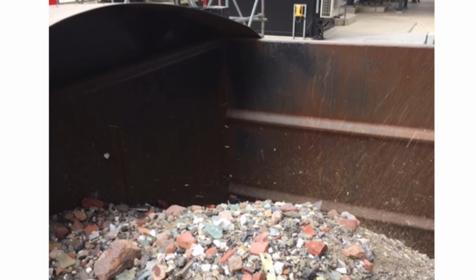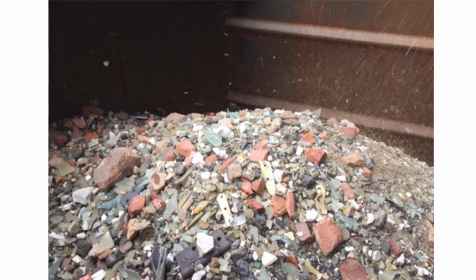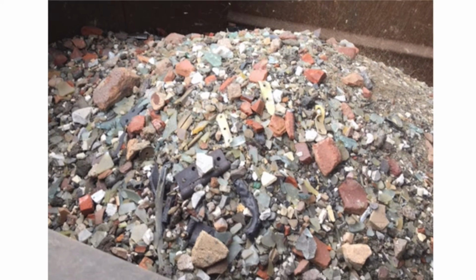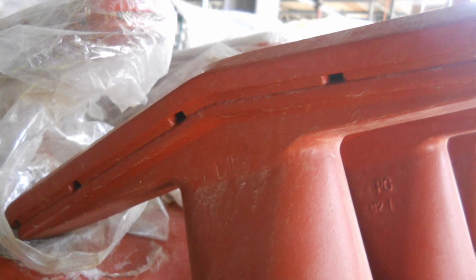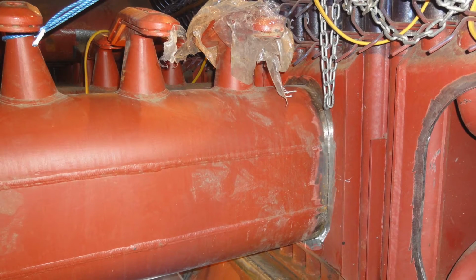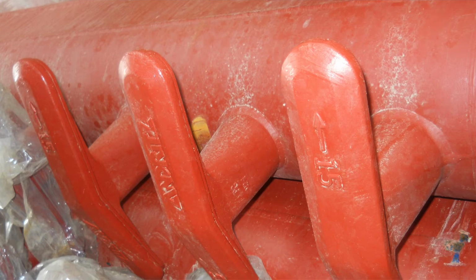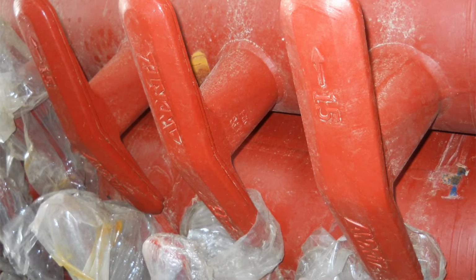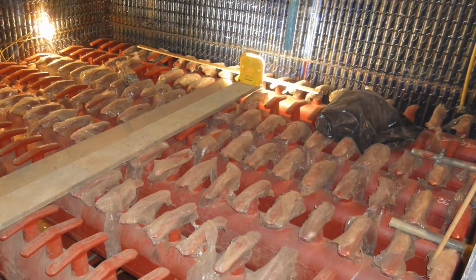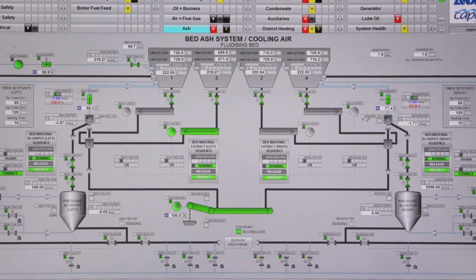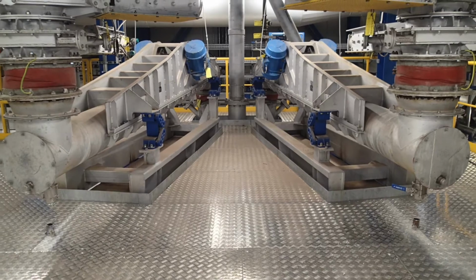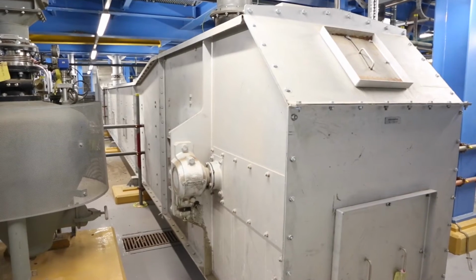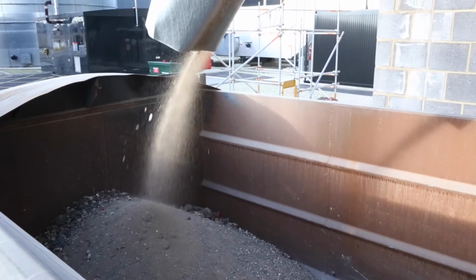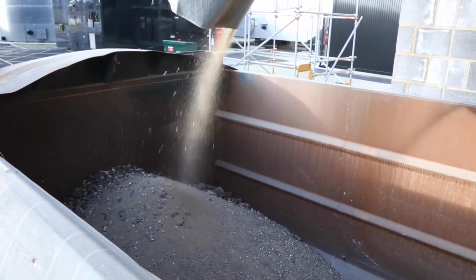Usually, the injection of coarse material like stones, nails, screws and metals cannot be entirely avoided. But with a properly designed nozzle grid, their negative effects like agglomerations in the bed can be significantly reduced. Andritz's proprietary design of the open nozzle bottom ensures that the coarse particles are constantly removed, and thus the optimum particle size fraction can be maintained. The air-cooled nozzle bars are positioned in such a way that the extraction even of larger particles is facilitated over the whole bed area. These nozzle bars are designed to avoid the clogging of the bed by wires and metal strips. This design has proven reliability at the hardest conditions, like the combustion of treated waste.